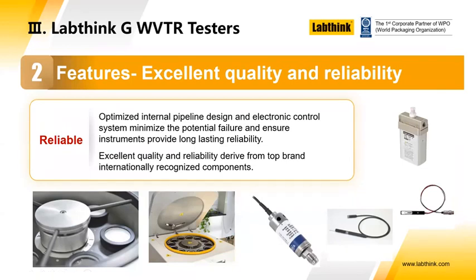The components inside obviously are important because the accuracy of the system depends upon the accuracy of each of the individual components. So we need to make sure that we use very top quality components for the load cell, for the humidity sensors, for the pneumatic connections, for the airflow measurement, etc., because all of these things add up to have a degree of error in them. They have a tolerance, and you add up the tolerances or the errors to get a stack of errors, and that's going to determine how accurate the end result is. So it's very important to use very good quality, reliable components with very small, tight tolerances.